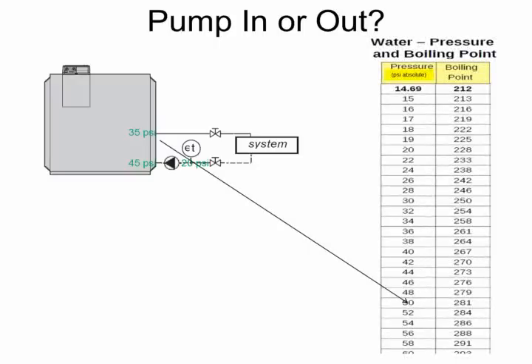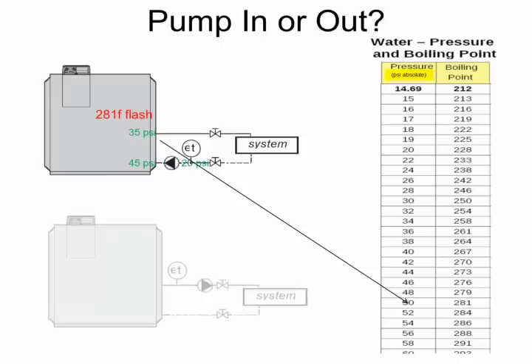At what temperature does boiling start to happen at 35 psi? Well, we can quickly look at a pressure-temperature chart from our engineering tool chest and see that 35 psi, which is 50 psi absolute pressure, will boil at 281 degrees. So our flash point is 281, okay?